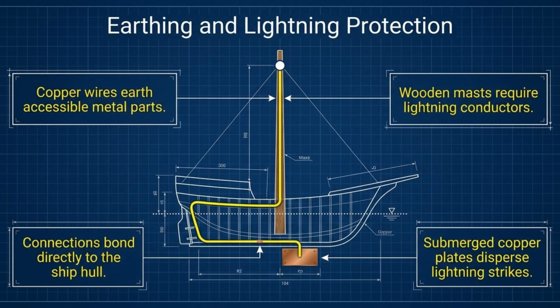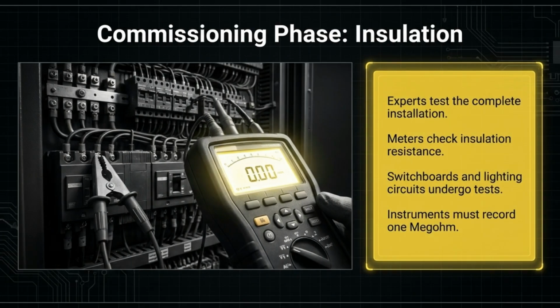Effective earthing and lightning protection are vital. Copper wiring bonds metal parts to the hull, and dedicated conductors help disperse lightning strikes safely into the water. During the commissioning phase, thorough insulation testing is performed. Experts use precision meters to verify that circuits meet the required megohm standards for safe operation.